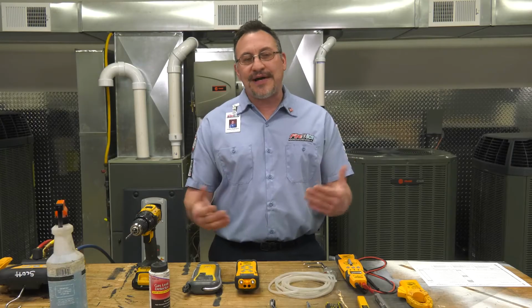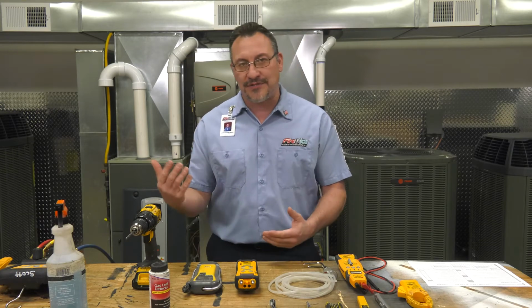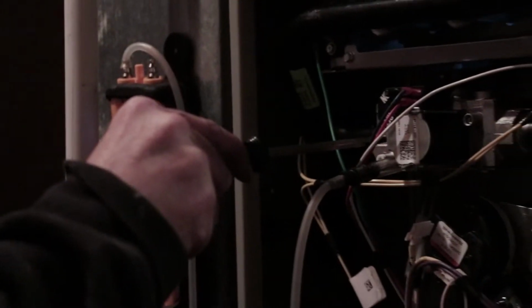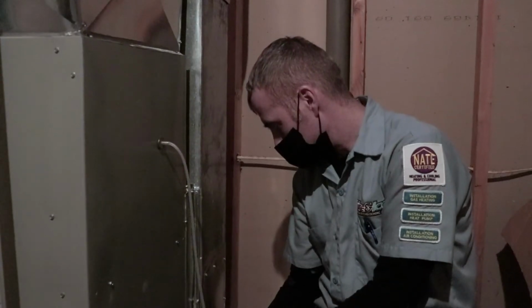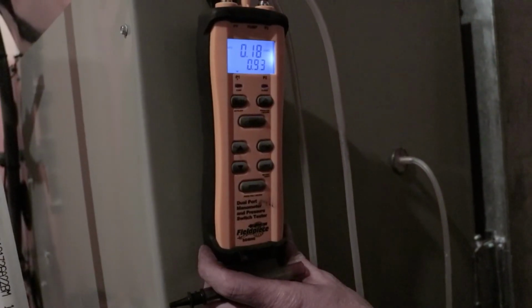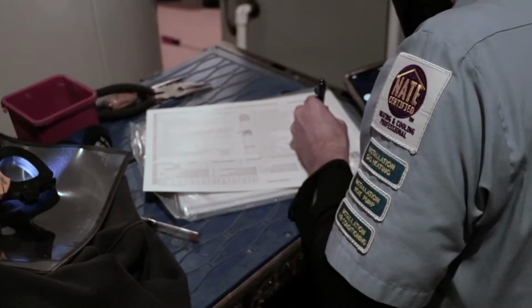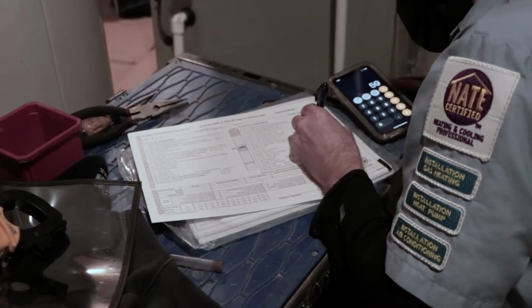This process cannot be completed until the system is completely installed and operable. We don't just hit the go button and walk away. We turn it on and let it run for a while, usually about 10 minutes per piece, 10 minutes for a furnace, 10 minutes for an air conditioner. Once we get beyond that, we start collecting data. This whole process usually takes somewhere between 45 minutes to an hour and a half, based on the equipment and whether we have a full system or just a furnace or air conditioner.